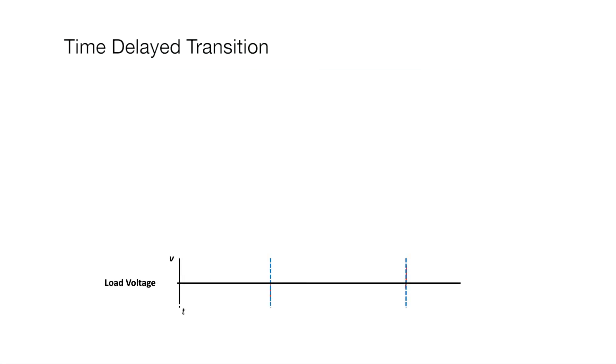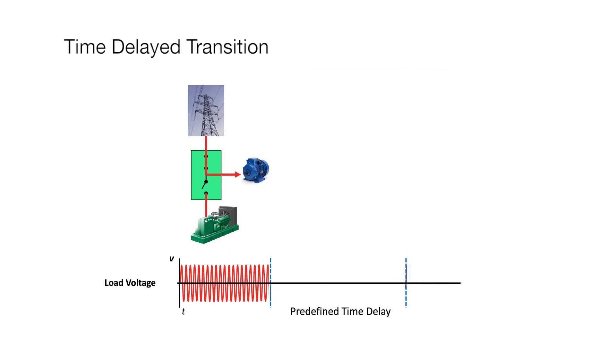In situations where the loads are large motors or other stored energy devices such as MRI machines, it is recommended to wait for some finite amount of time to allow the residual voltage on the load to decay to a safe level before transferring.